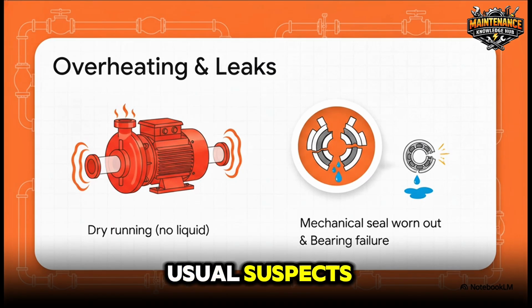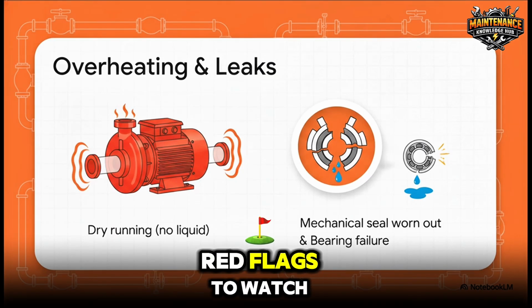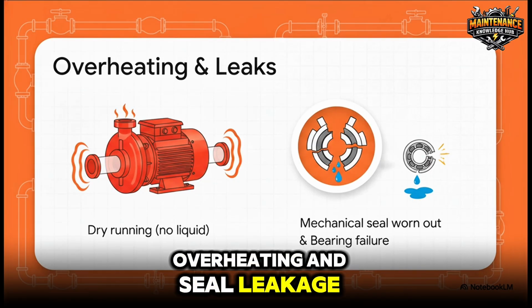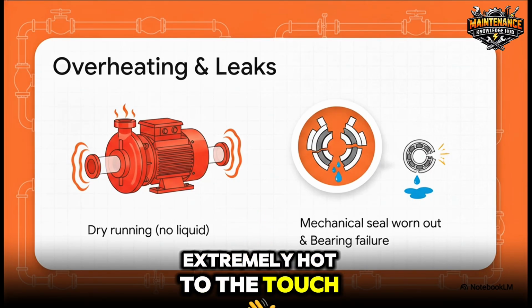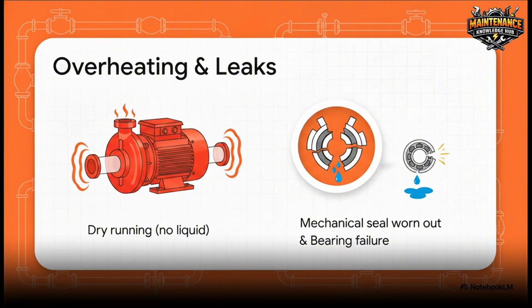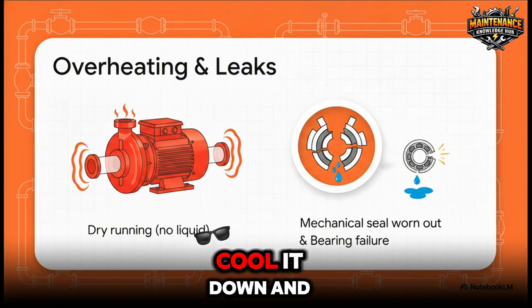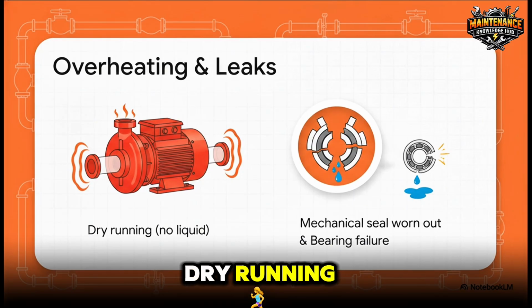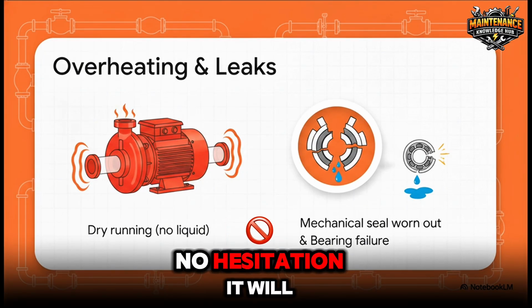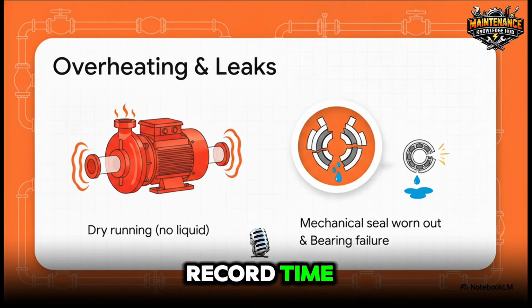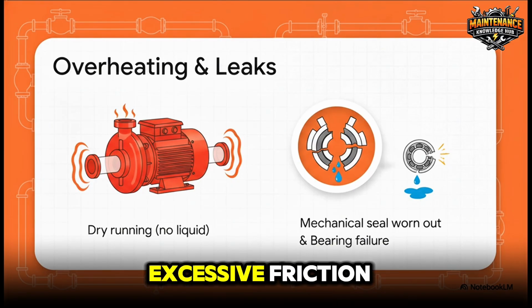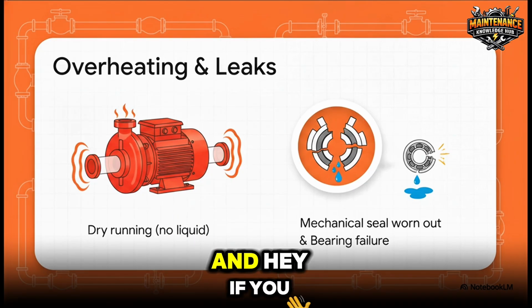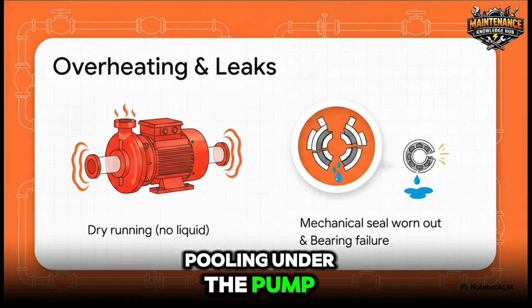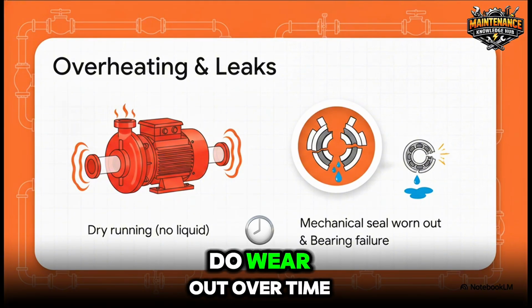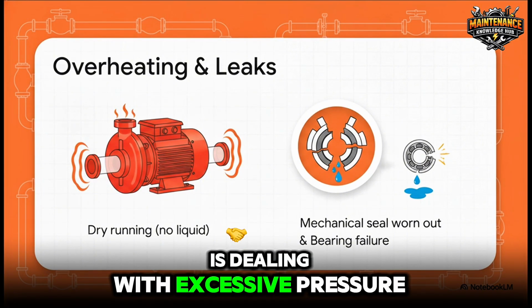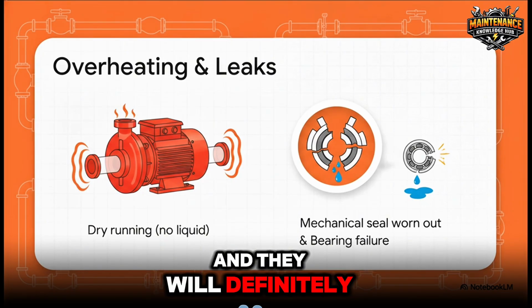To wrap up our usual suspects, we've got two massive red flags to watch out for: overheating and seal leakage. If that pump is extremely hot to the touch, it might be what we call dry running. This means there is literally zero liquid inside to cool it down and lubricate it. If you even suspect dry running, stop the pump immediately. No hesitation, it will completely destroy itself in record time. Overheating can also stem from bearing failure or excessive friction because something is misaligned. And hey, if you see puddles of liquid pooling under the pump, you need to inspect the mechanical seals. They do wear out over time, especially if the system is dealing with excessive pressure or a misaligned shaft, and they will definitely need to be replaced.